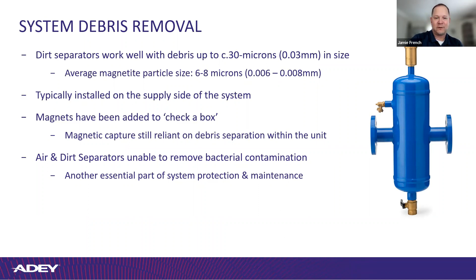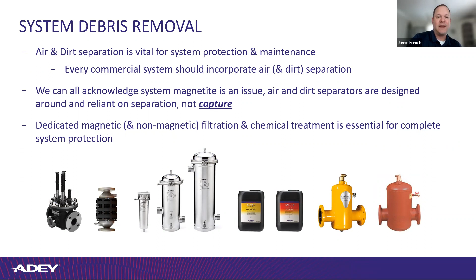And oh yeah, also important there, because we talked about the bacterial contamination. If these don't get serviced, then you have a spot for bacteria to start growing. So you want to make sure it's easy to service, and that's where we jump in with our ADEY stuff. But just to wrap it up, kind of bring it full circle, air and dirt separation is vital. Every commercial system should have it and will have it. But we can acknowledge that magnetite is still an issue because the air and dirt separators are looking to separate and not necessarily capture. So you need a dedicated magnetic and non-magnetic filtration and chemical treatment in order to make a complete system protection, right?